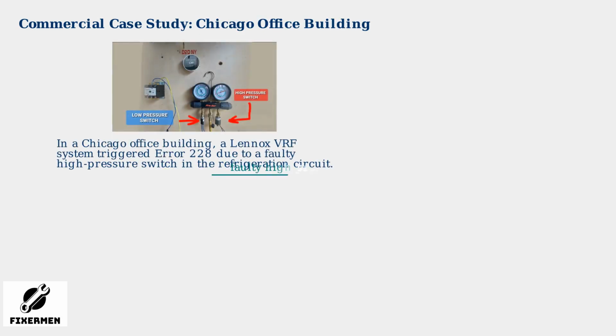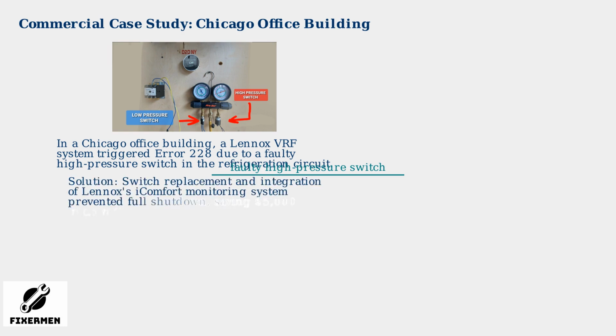In a commercial example from a Chicago office building, a Lennox variable refrigerant flow system displayed error 228 caused by a malfunctioning high-pressure switch. This switch failed to properly monitor the discharge line pressure, leading to the fault condition. The resolution included replacing the faulty switch and implementing Lennox's iComfort monitoring system for real-time diagnostics. This proactive approach prevented a complete system shutdown, ultimately saving $5,000 in potential downtime and productivity losses.